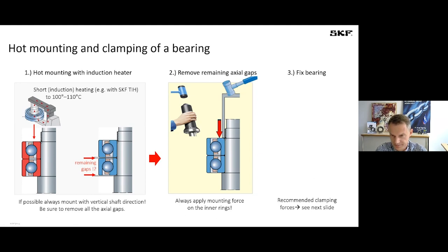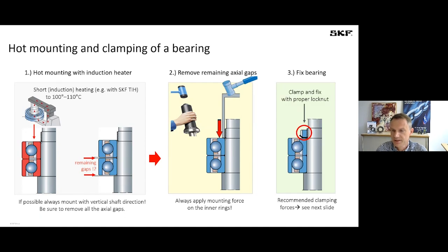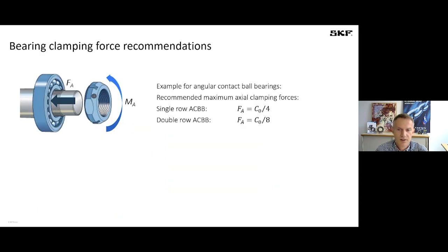And then you fix the bearing with a proper lock nut. Often the question also comes up, what should be the mounting torque of the lock nut or the axial clamping force? SKF has for different types of bearing different recommendations. Here you see some recommendations for angular contact ball bearings based on the static load capacity which you find in the catalog.